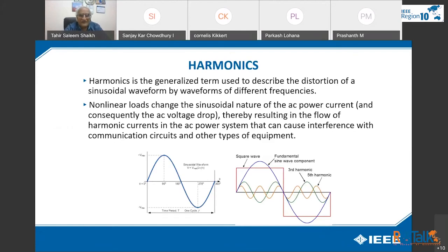Harmonic is a generalized term used to describe the distortion of a sinusoidal waveform by waveforms of different frequencies. A non-linear load changes the sinusoidal nature of the AC power current and consequently the AC voltage drop, thereby resulting in the flow of harmonic currents in the AC power system that can cause interference with communication circuits and other types of equipment. So this diagram shows what will be disturbed by harmonics. The harmonics will create frequencies that are multiples of the base frequency.